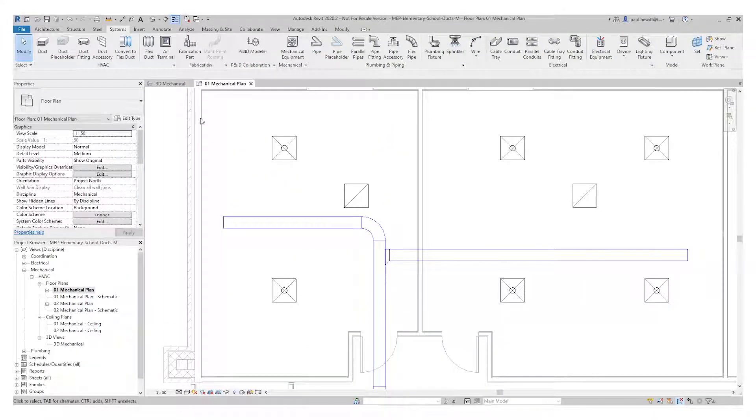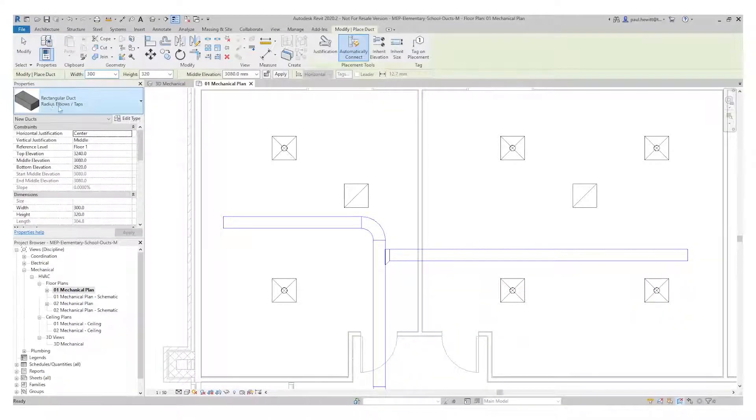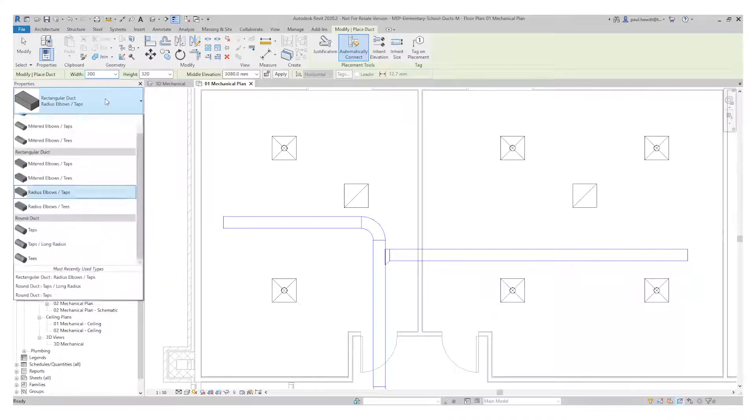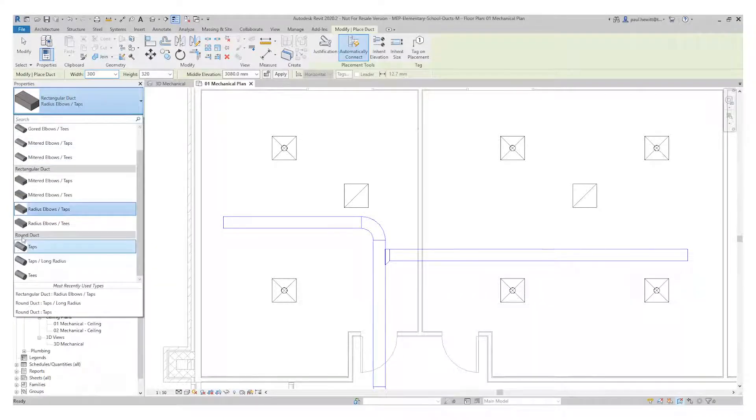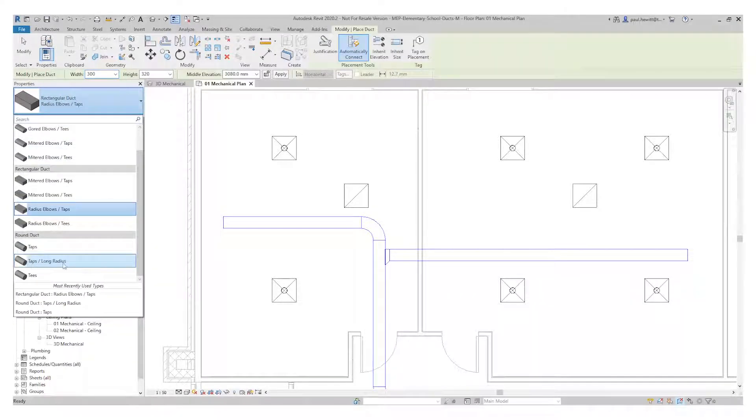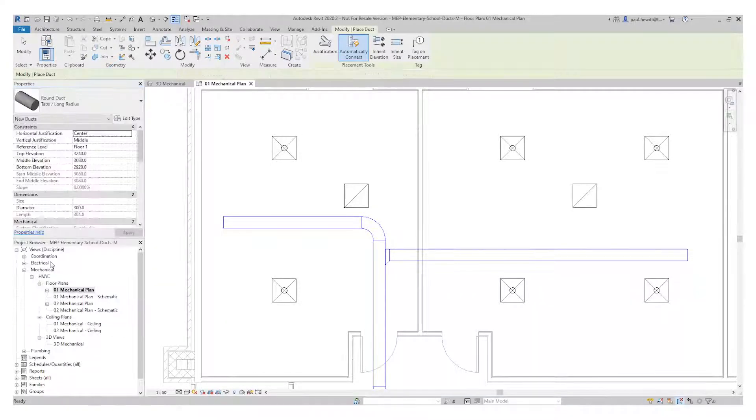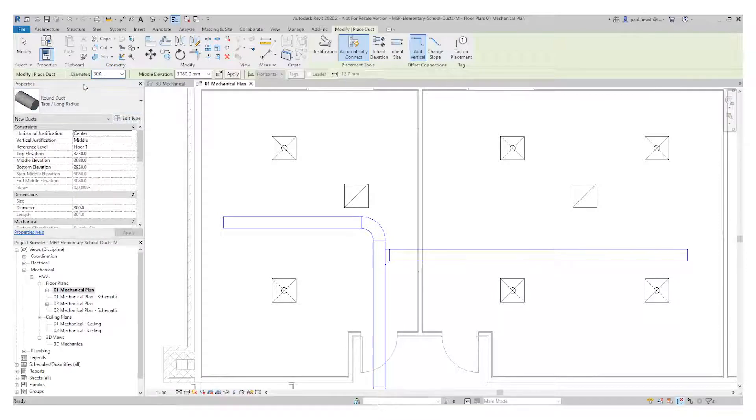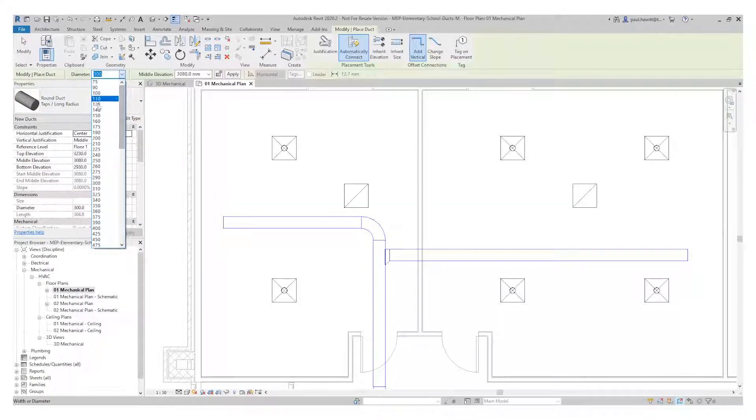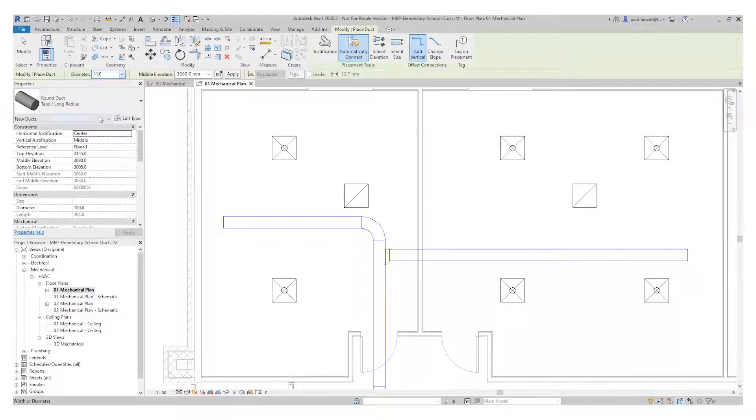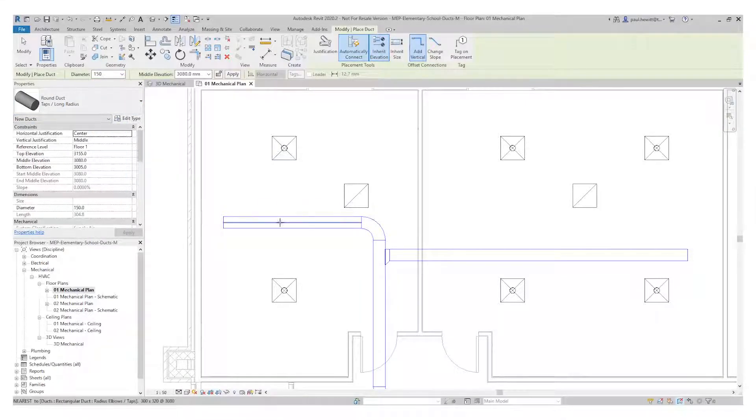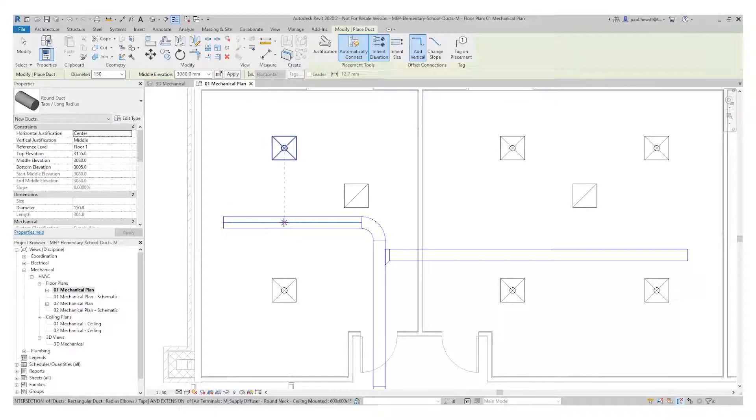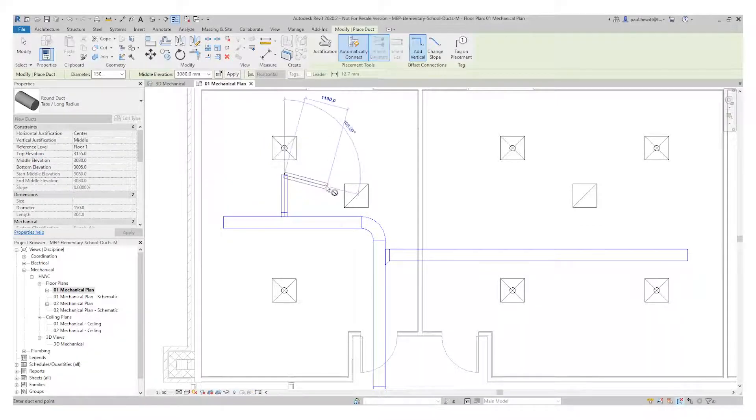And then I'm going to use the duct command again but changing the type to round duct and we use the long radius option. I'll also need to change the size to 150 and also I need to inherit the elevation. So I select the inherit elevation switch to keep it the correct height.